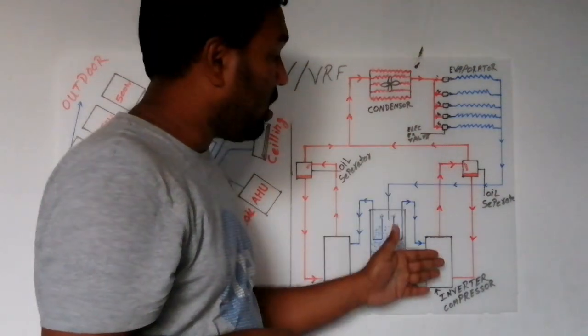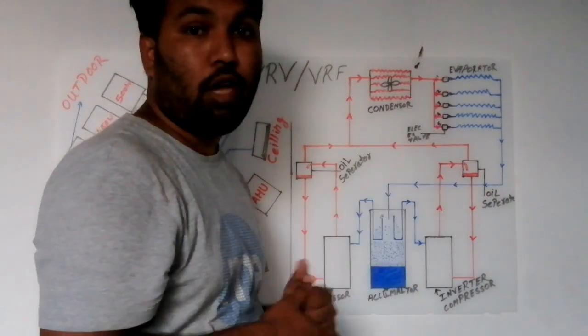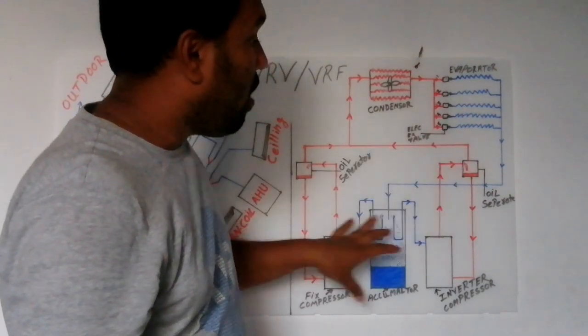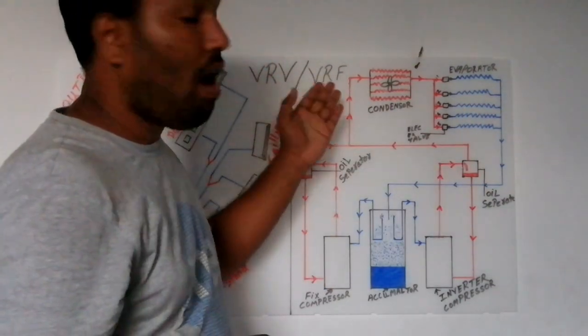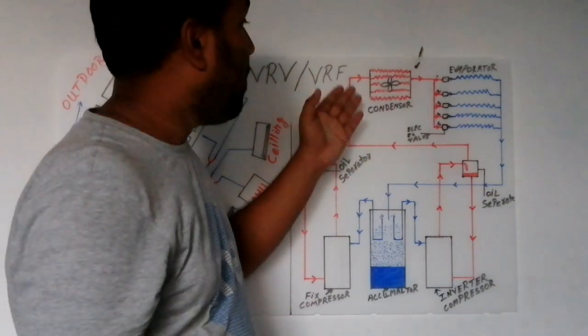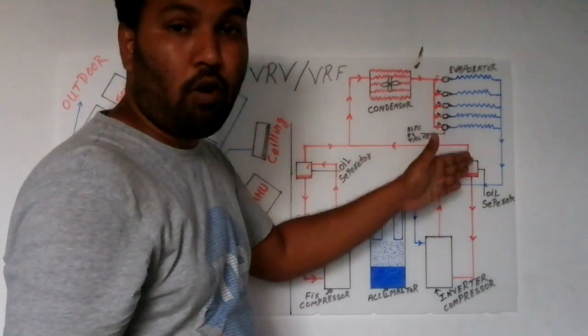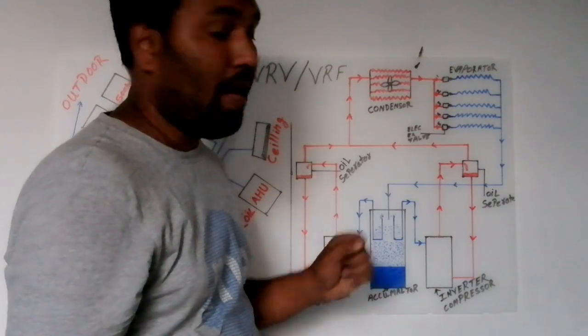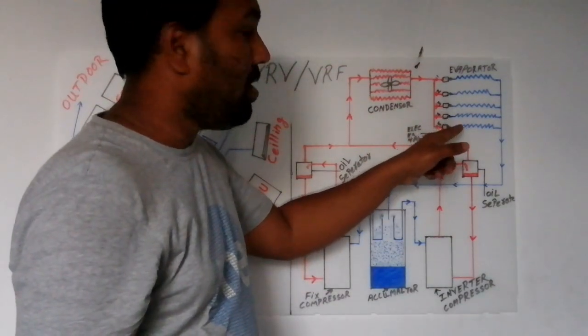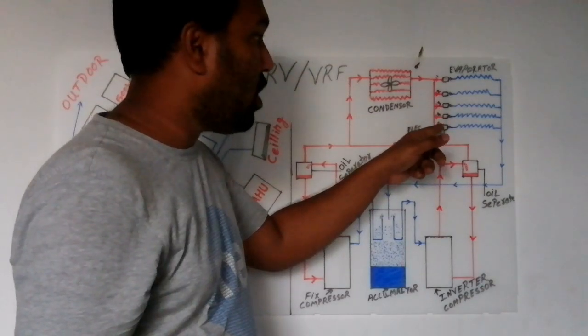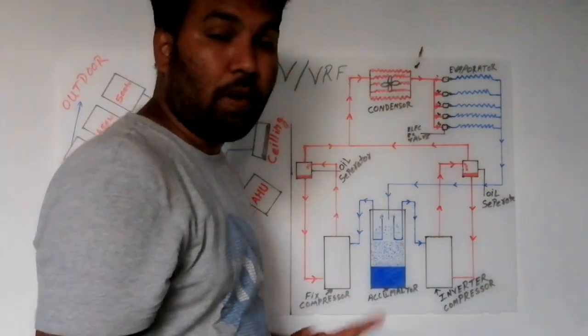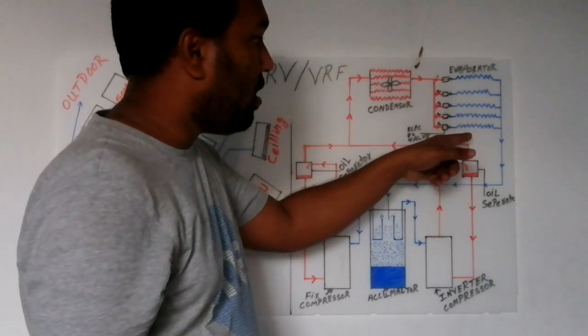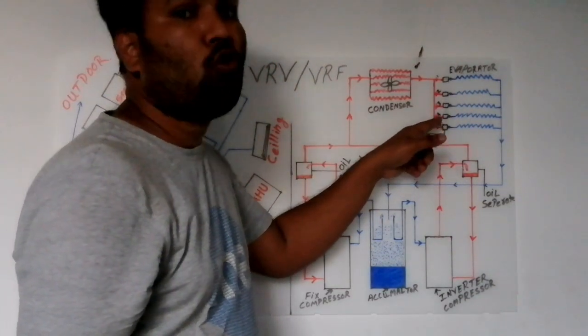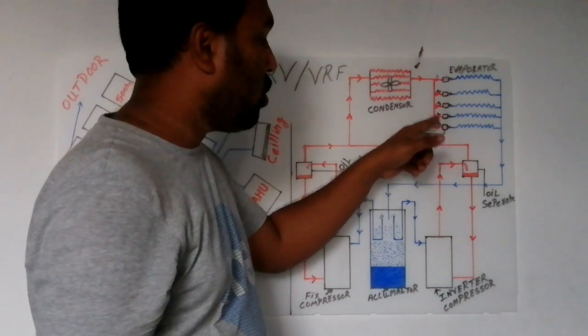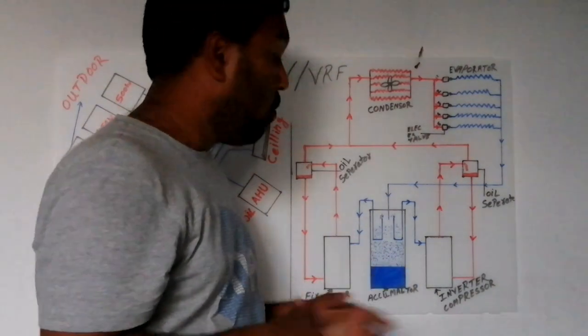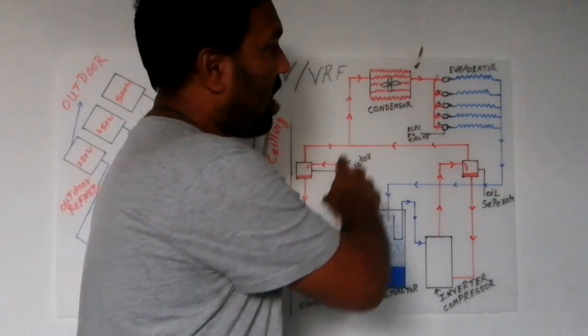As we know, the inverter compressor works according to the load of our evaporator coil. Due to this cycle of the inverter compressor, we call it VRF, meaning variable refrigerant flow. Variable refrigerant flow: it flows to all the evaporators by controlling the electronic expansion valve. Whatever the requirement is in our evaporator coil, each expansion valve gives different commands to our compressor. According to the demands of our evaporator coil, when it needs more refrigerant, our expansion valve gives commands to the compressor to work more frequently. This is the basic refrigerant cycle of a VRF system.